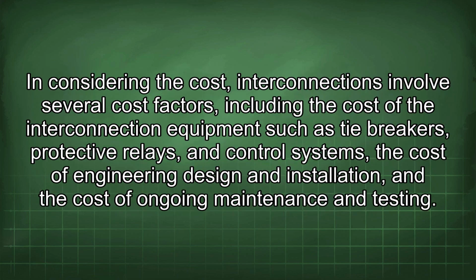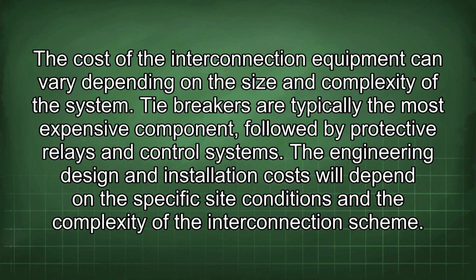In considering the cost, interconnections involve several cost factors, including the cost of the interconnection equipment such as tie breakers, protective relays, and control systems, the cost of engineering design and installation, and the cost of ongoing maintenance and testing. The cost of the interconnection equipment can vary depending on the size and complexity of the system. Tie breakers are typically the most expensive component, followed by protective relays and control systems. The engineering design and installation costs will depend on the specific site conditions and the complexity of the interconnection scheme.